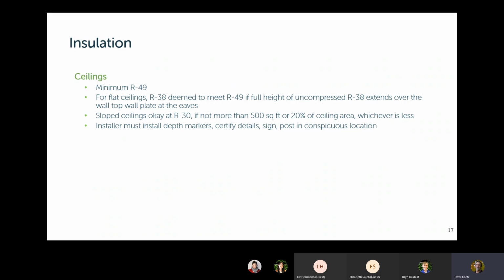The code does have other language in it. You're allowed lower levels of insulation in the attic if you can get your full height all the way out over the outside walls. Some of you probably realize this is often not possible because of the clearance between the top of the exterior wall and the underside of the roof sheathing at the two eave edges. So the R49 applies if that's the case, but if you can get at least R38 over everything, you only need to do R38. Slope ceilings have the same requirement actually, although if you only have a small quantity of slopes in the house, you are allowed R30 rather than R38.